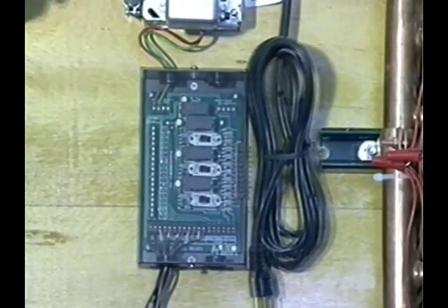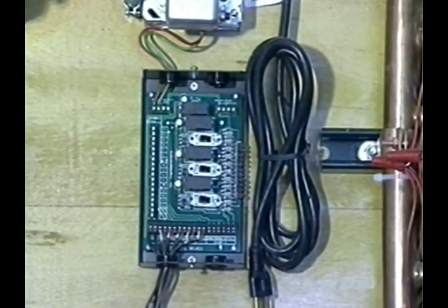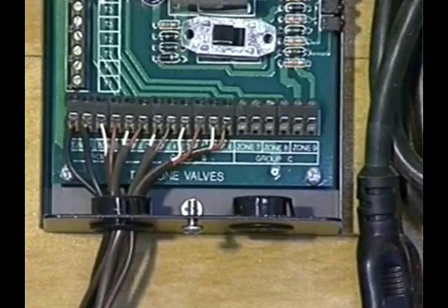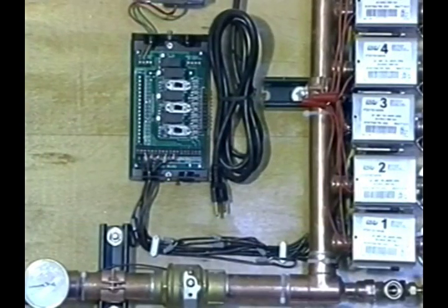Wiring comes next. Use a control box to help tie in all zone valves, thermostats, and your secondary pump. If using an indirect water heater, some control boxes come with a hot water priority. This makes sure your domestic water needs are always met. A control box provides a neat and centralized installation of your radiant floor control wiring. The control box also connects to your boiler. This completes the wiring of the system.